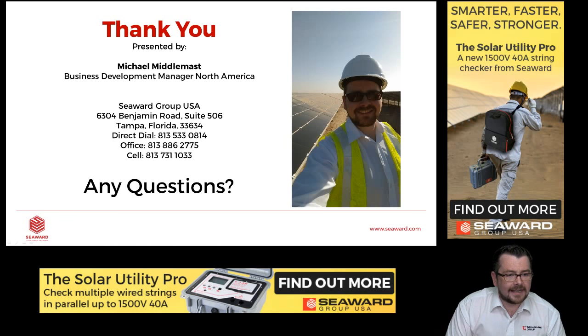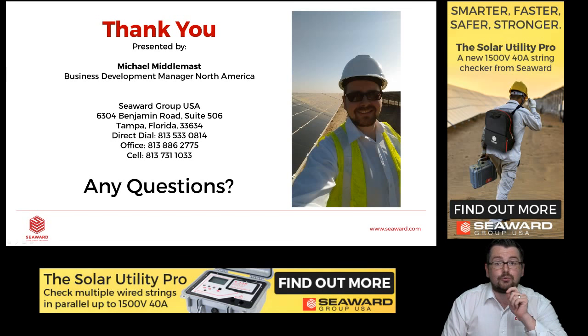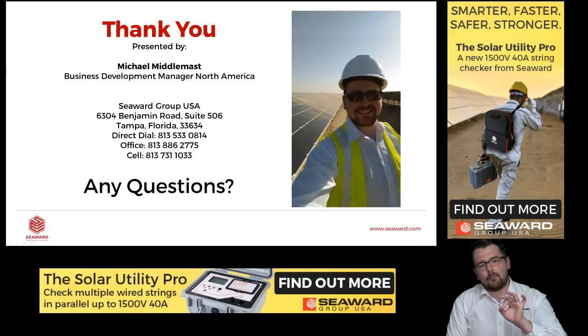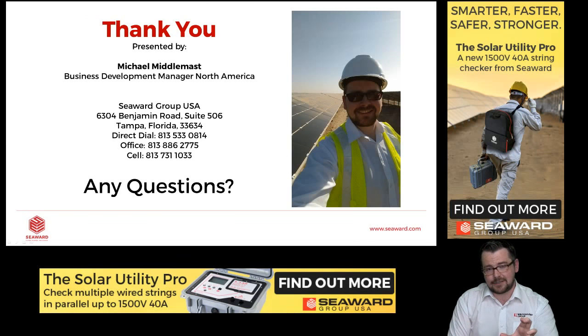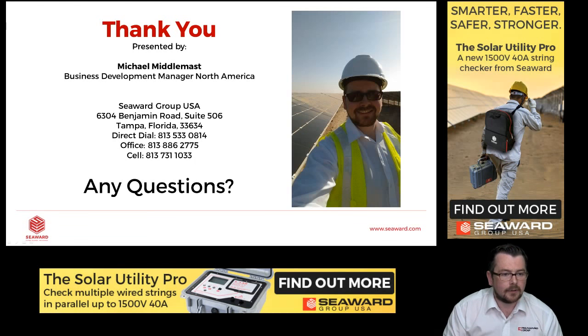Yatin Shnar asks, what should positive to ground and negative to ground voltage be on a healthy array? So when we're doing positive to ground and negative to ground, we're not measuring voltage, we're measuring insulation resistance. So we're measuring resistance, and that's actually in mega ohms. And the IEC 62446 standard tells us that should be at least one mega ohm. So I would advise going to take a look at that standard.